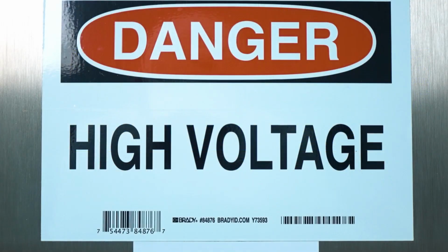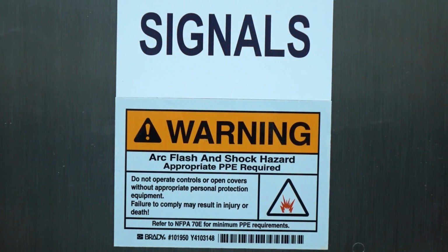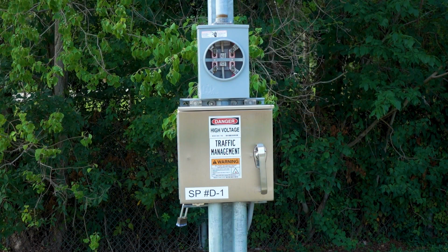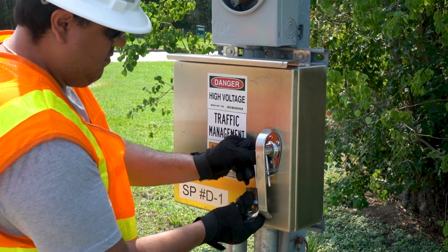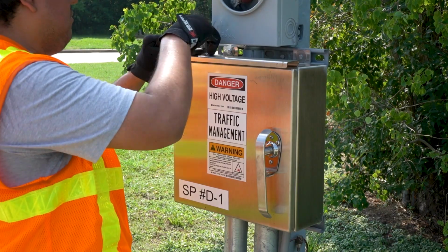All service enclosures are to be provided with an OSHA high-voltage label on the exterior surface of the door, along with an arc flash warning label, as required by the NEC. The enclosure must also be labeled to indicate the unique service ID, as shown on the electrical service data chart in the plans, and the type of load served. The enclosure door is equipped with a padlock for security.